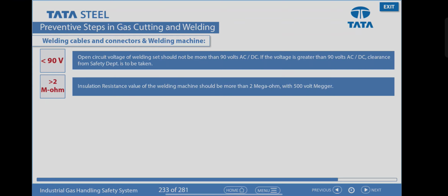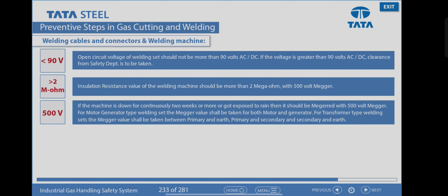Insulation resistance value of the welding machine should be more than 2 megaohm with a 500 volt megger. If the machine is down continuously for 2 weeks or more or got exposed to rain, then it should be meggered with a 500 volt megger. For motor generator type welding sets, the megger value shall be taken for both motor and generator. For transformer type welding sets, the megger value should be taken between primary and earth, primary and secondary, and secondary and earth.